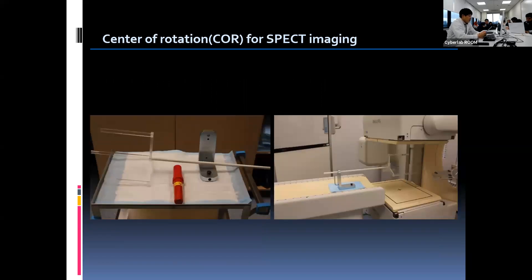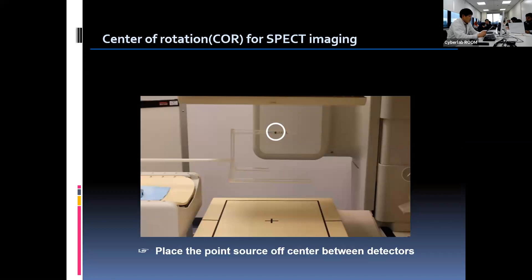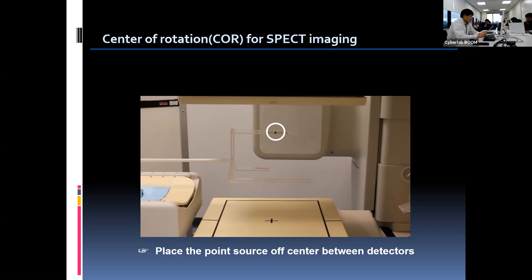For the COR test, we need 500 microcuries of technetium point source and a supporting fixture to hold the source, as shown in the picture on the right. Manufacturers may offer proper devices for their machines, and required items and test methods may differ between camera brands. Once the point source is placed off-center between detectors, SPECT acquisition can start. Different COR tests should be performed for each collimator that is practically used for clinical imaging, since different weight and fit of the collimator may affect variation. In cases where the camera is used in a 90-degree head position for cardiac study, COR testing should be done in 90-degree separation as well as in the 180-degree position.